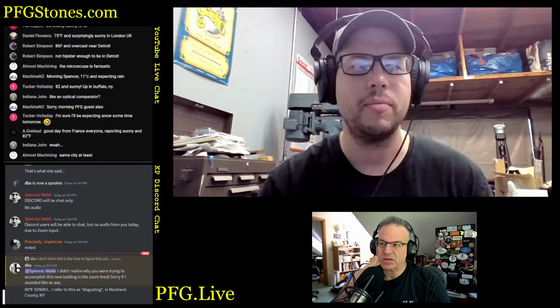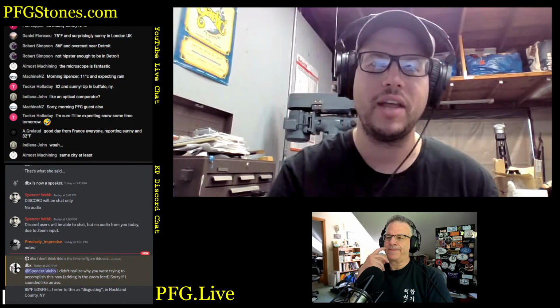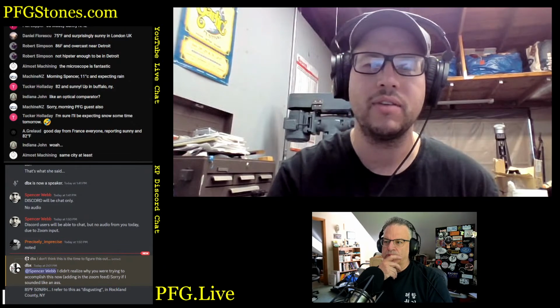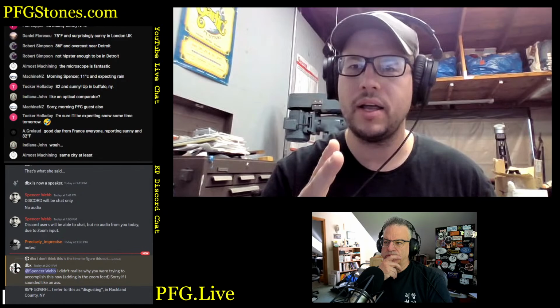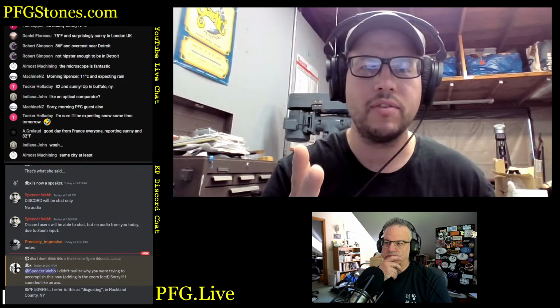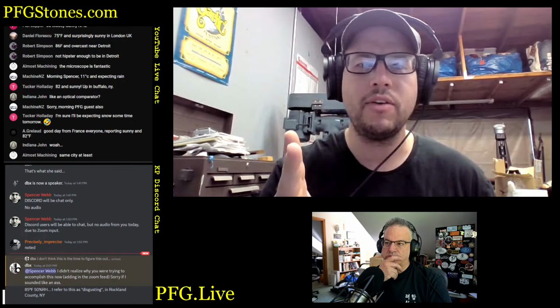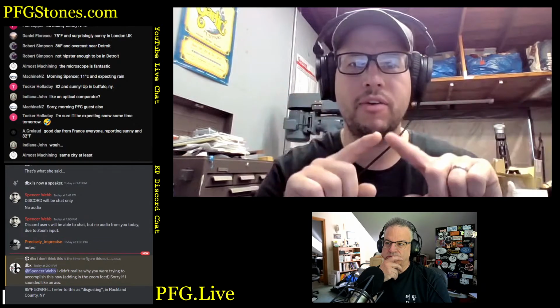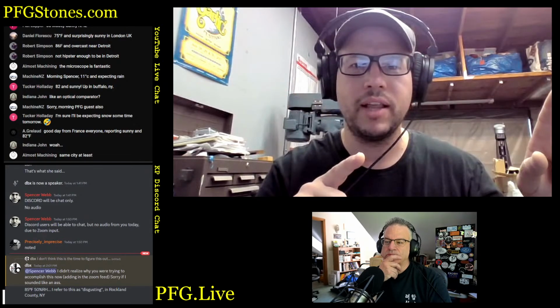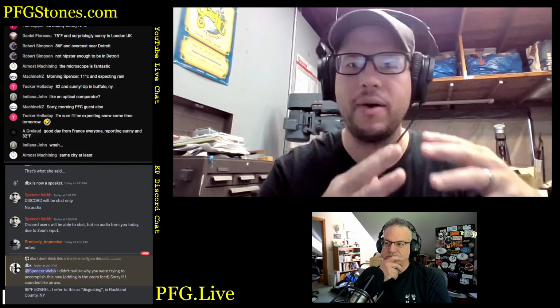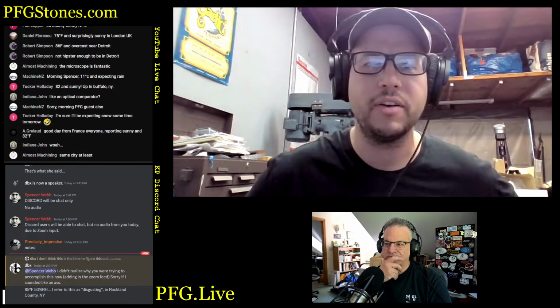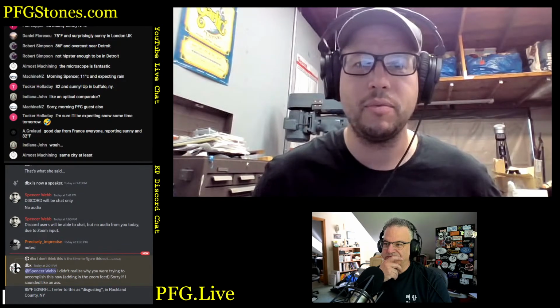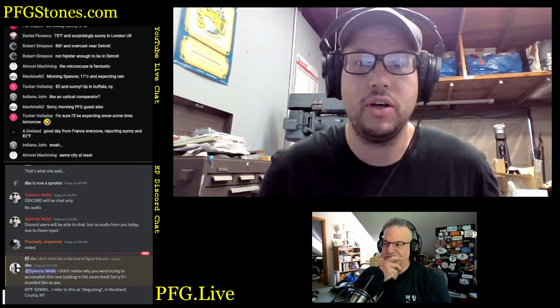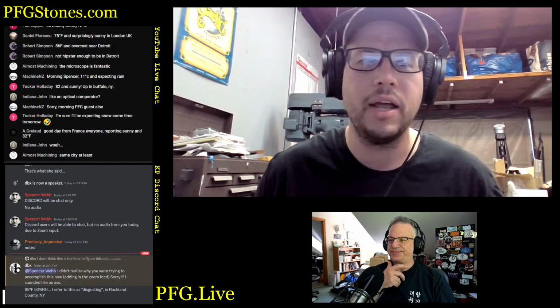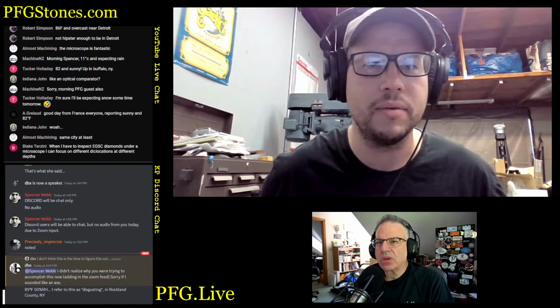But the crazy thing to me is that it then also is able to link that to the scales, because if you only link the objectives and the CCD, then you can measure on screen, but you can't measure outside of the field of view. That's where the scales come in. And it somehow links all of that up. That is also not clear to me, but I've measured many things with it, and it's good. I verify it compared to mechanical measurements that I do, and it's really quite good.